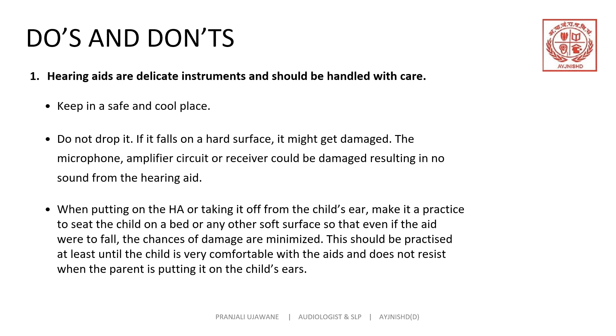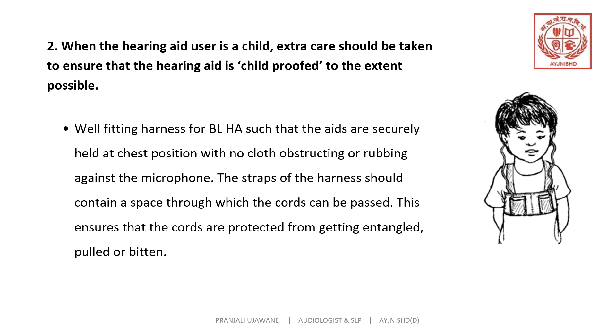Use a well-fitting harness for the body level hearing aid, such that the aids are securely held at the chest position with no cloth obstructing or rubbing against the microphone. The straps of the harness should contain a space through which the cords can be passed. This ensures that the cords are protected from getting entangled, pulled or bitten. It is shown in the picture. You can just imagine how the harness should fit on the child's body so that we can put the hearing aid properly.